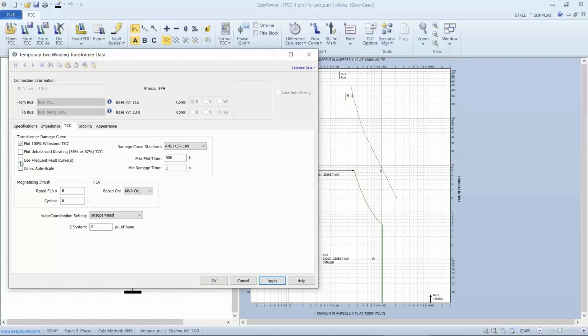Secondly, let's invoke our frequent fault curve by checking that third box and applying it. Now we know that the upper part of the curve is thermal damage, and the lower part of the curve is mechanical damage from the magnetic impulse. And so this is a frequent fault plot line that's described in the ANSI standard, and given specific transformer conditions or parameters, the transformer will survive a limited number of excursions through this area, through this portion of the curve. So to be conservative, we want to coordinate against that and make sure, when at all possible, we avoid exceeding that guideline.